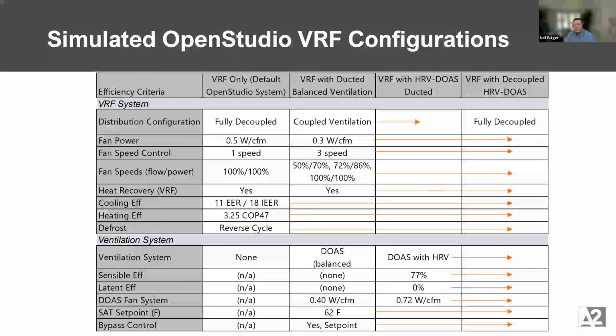The high energy use was if we had single speed fans and they had ventilation delivered, you get really bad performance. Kind of makes sense. We're almost modeling something that doesn't exist. We're modeling an energy model that's always at 100% airflow, even if it might have some modulating capacity. We saw probably a more realistic answer for what VRF would look like, even if it had ducted outside air to it, would be this three-speed fan control, a little less pressure because now we have another fan providing power. And then the same as we step through this, we're adding heat recovery, increasing the DOAS fan pressure, and then lastly, decoupling those fans, letting them cycle.